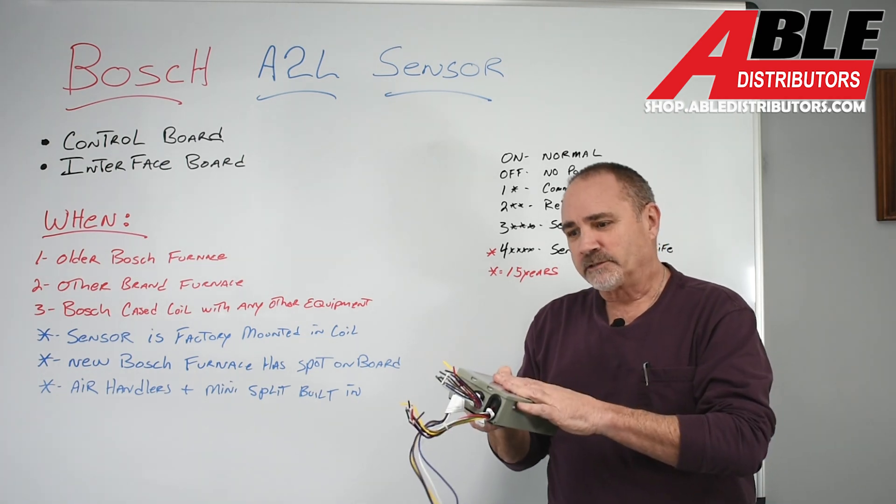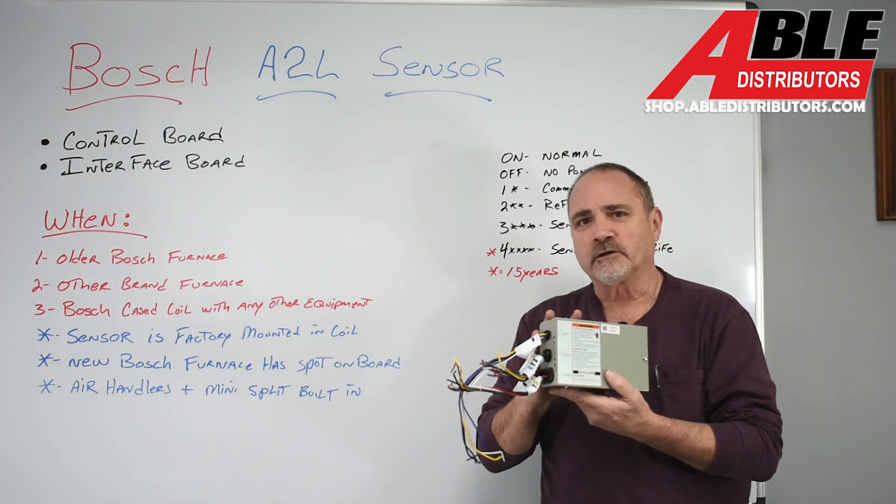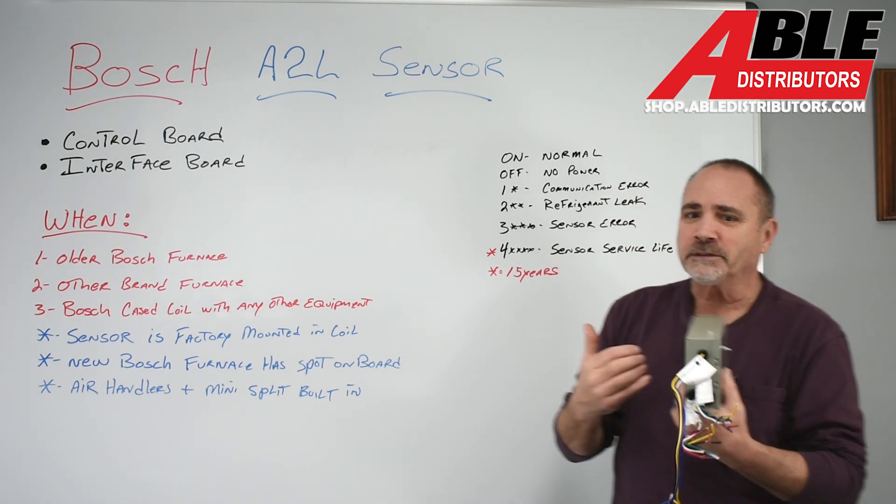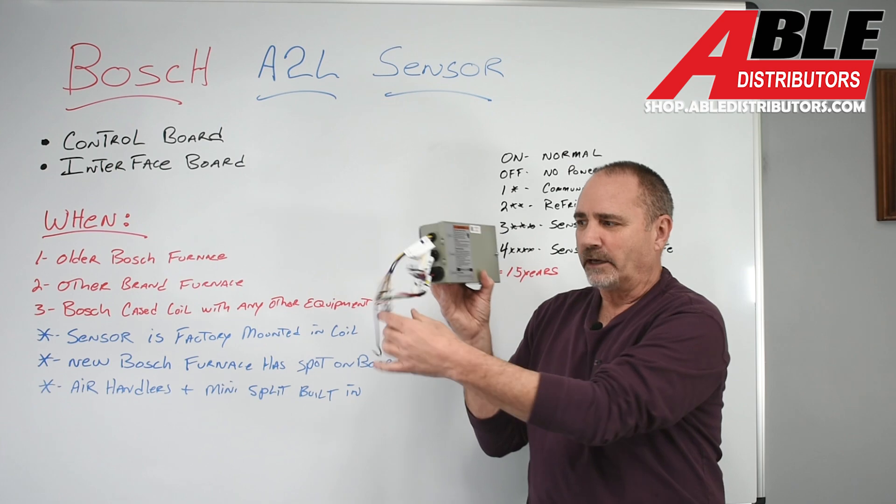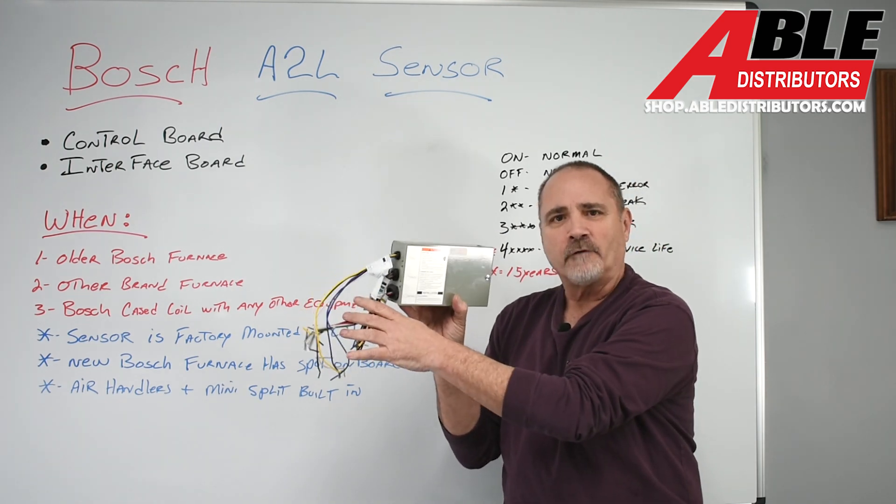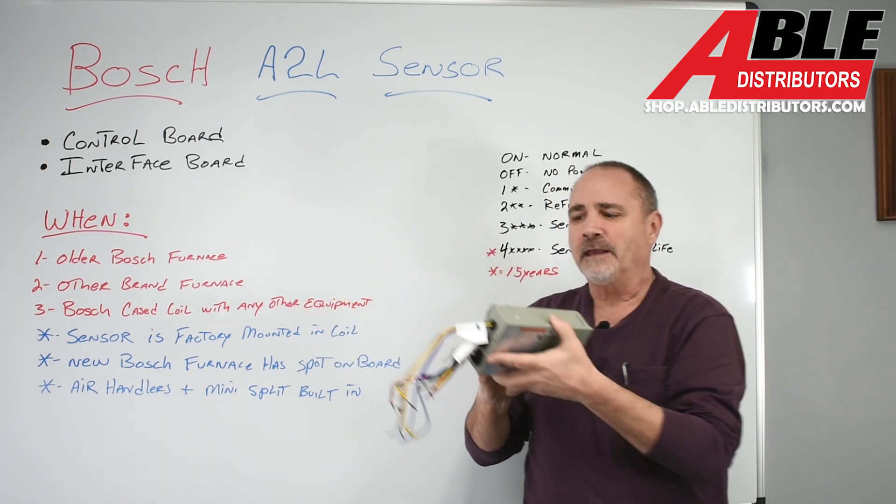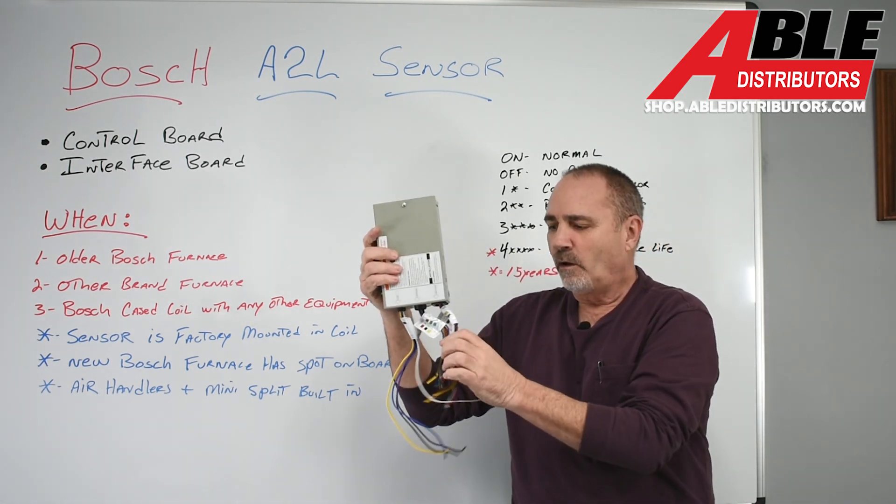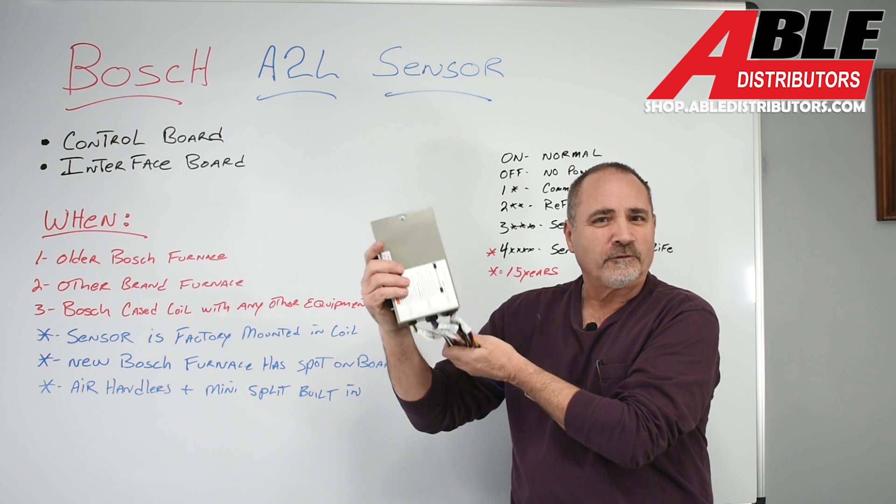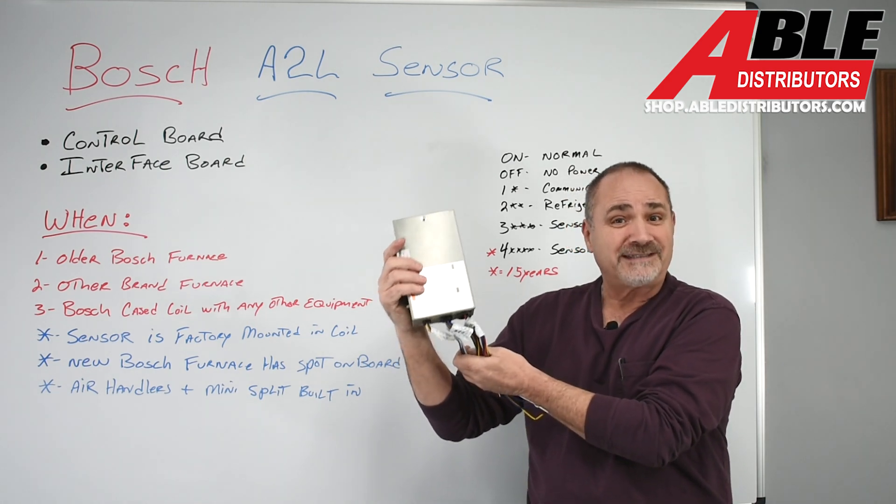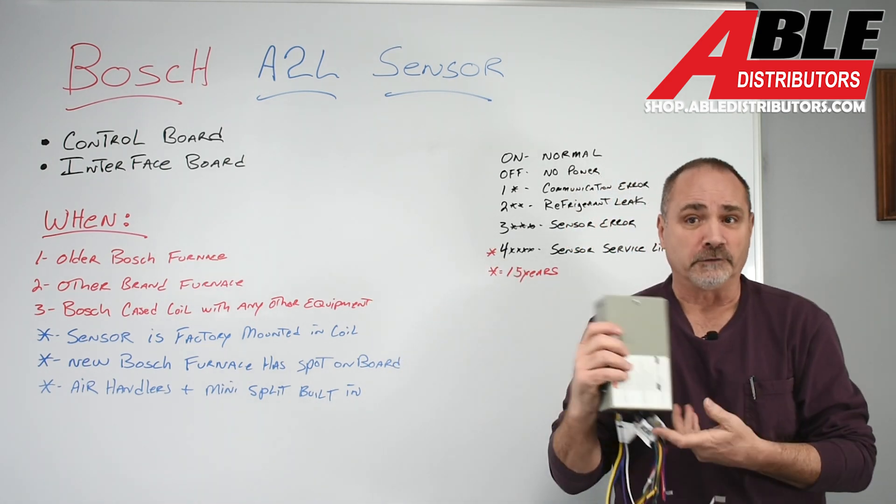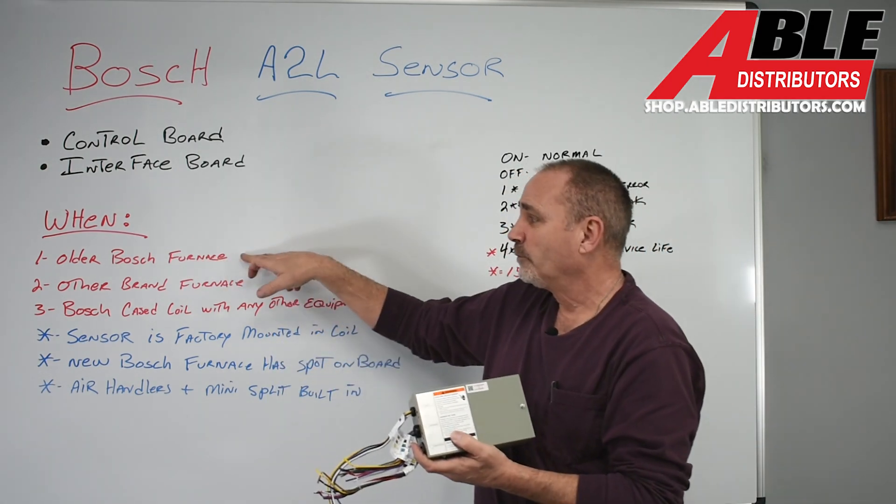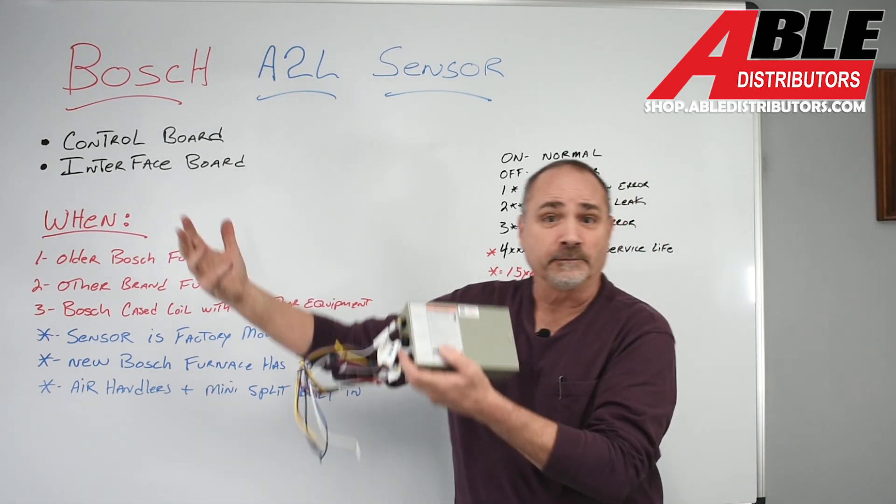So mounting this box. Now Bosch gives you a little sticker on where to mount this on the A-coil. This is the only thing. Personally, I don't think I would mount this on the A-coil and have a bunch of wire nuts dangling off in mid-air on my install. I think I would mount this probably down near the furnace, drill a hole, bring these wires into the furnace cabinet so all my wire nuts, all my mess is kind of concealed and my job looks really, really good. So again, you'll only need this older Bosch, other brands, or if you put their coil on something else.